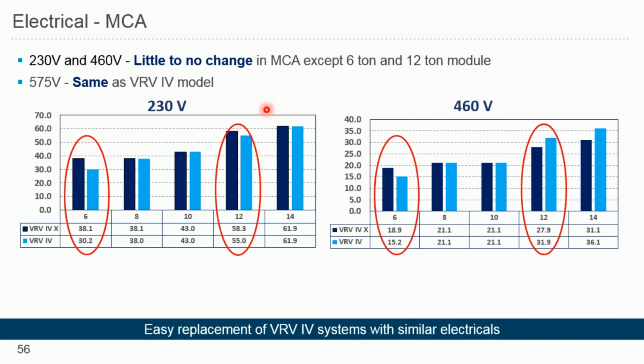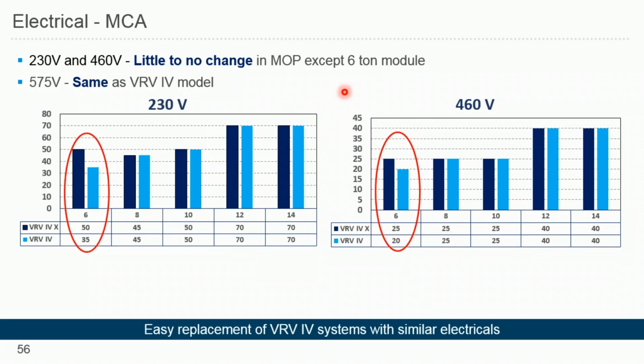For 575-volt models, there's not going to be any changes happening for VRV4 models. MOPs, again, for the 6-ton model, keep in mind the MOP level will be a little bit higher for both 230 and 460-volt models. No changes on the 575-volt model. But overall, if you're switching from VRV4 to 4X, if you're using 8, 10, 12, 14-ton models, there's not much that you have to be worried about in terms of the electricals.